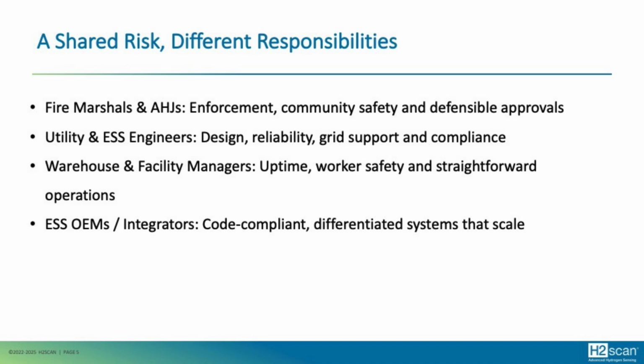But as soon as you put those forklifts or charging areas in a confined space, then the authority having jurisdiction might require you to lower the amount of hydrogen that's permissible in that area, just to avoid any kind of fast accumulation. It's also, as far as facilities managers, making sure that systems are maintained and that uptime is the most important when it comes to not only the forklift equipment and the batteries, but also worker safety, and make sure that the safety systems are also properly maintained. And then, of course, making sure that we understand the codes that affect each area. So as we move from state to state, these codes and regulations can change, and also as we move from city to city. So there are slight variances in the way different jurisdictions handle code compliance. And so make sure you understand what is required in your area.